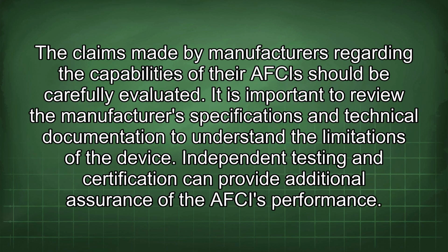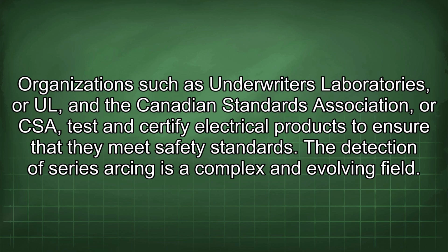The claims made by manufacturers regarding the capabilities of their AFCIs should be carefully evaluated. It is important to review the manufacturer's specifications and technical documentation to understand the limitations of the device. Independent testing and certification can provide additional assurance of the AFCI's performance. Organizations such as Underwriters Laboratories, or UL, and the Canadian Standards Association, or CSA, test and certify electrical products to ensure that they meet safety standards.